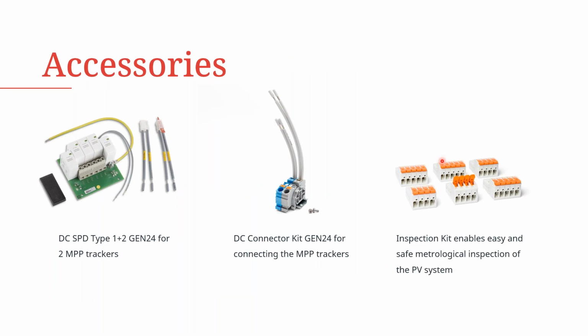When using the Gen24 and Gen24 Plus inverters, there are some accessories you can opt for. Starting with the DC SPDs, there's a print board with type 1 plus 2 SPDs for the Gen24, including protection for the two MPPTs. There's also a DC connector for connecting the MPPT trackers, especially needed when you have to pre-combine your DC array or PV array, requiring the DC connector kit.